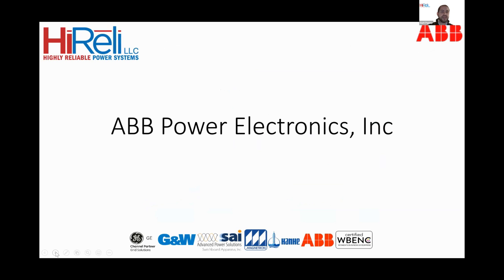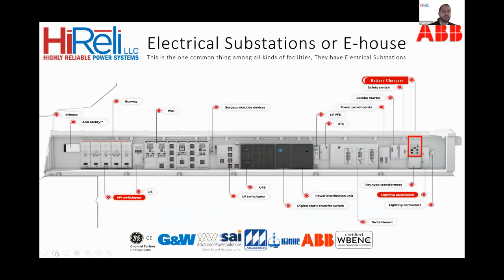So moving along to ABB and the power electronics side. Which battery chargers are we referring to? Here you have the common electrical substation control house, or E-house, where you have your medium voltage, low voltage switchgears on the left to right. You have UPS systems, transfer switches, switchboards, panel boards, etc. And then you have the battery charger there that's highlighted with the red box. These battery chargers provide the charge to your station's battery banks that power the DC load within the substations.